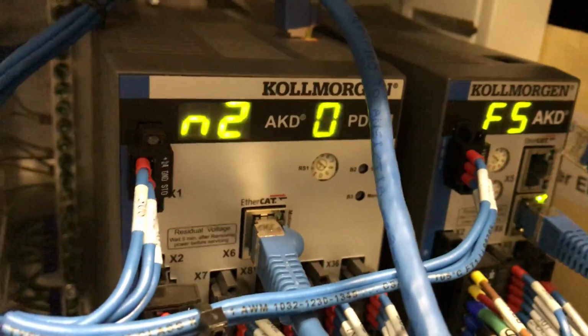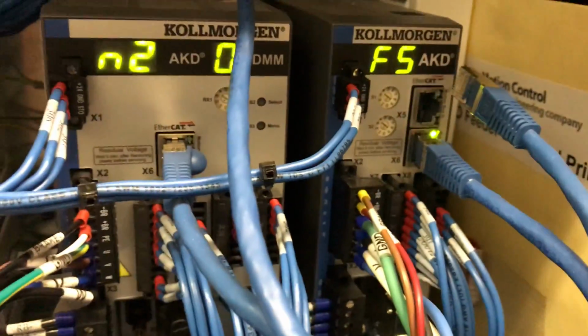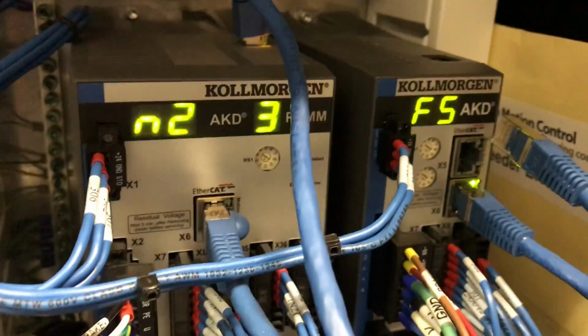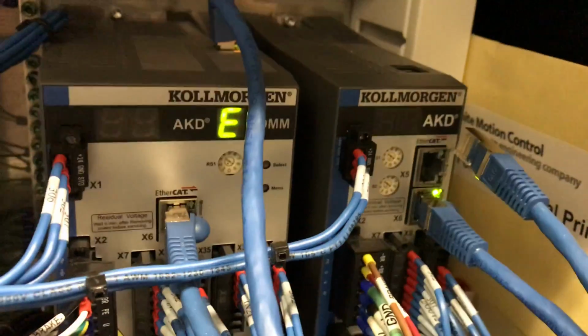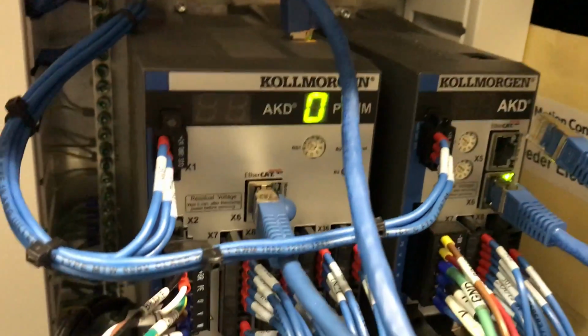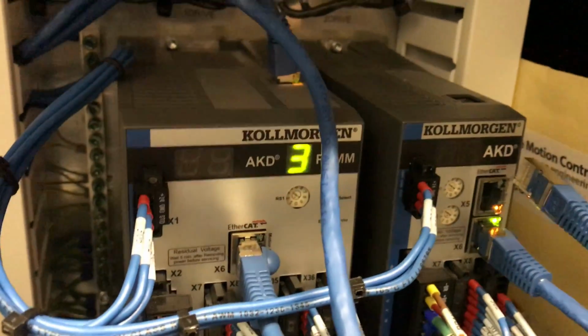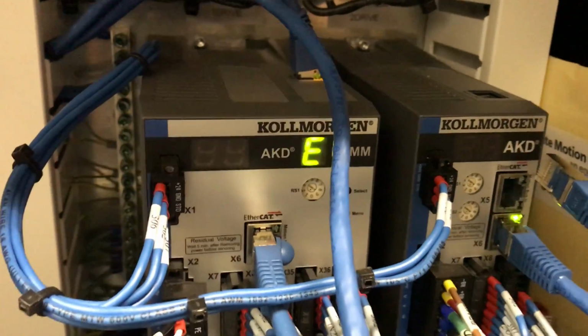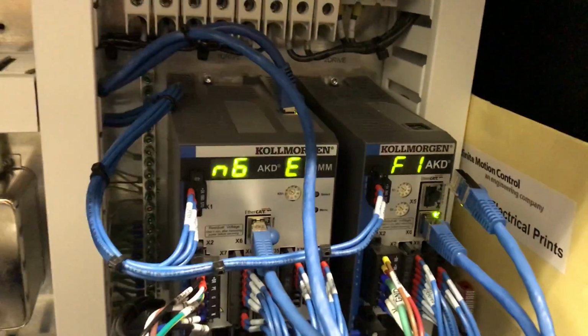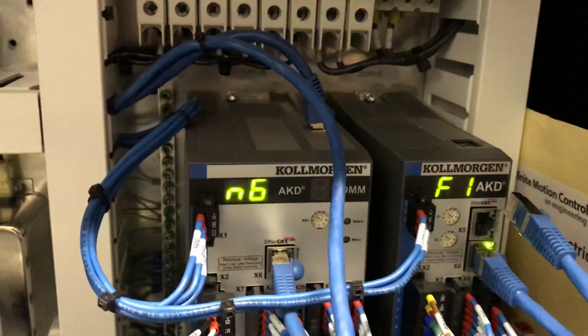It could be that the EtherCAT communication has failed, which it has in this case because I unplugged it, or it could mean that one of these devices has failed. There are other codes as well. Another one that's common is E33. That means that the configuration isn't what is expected, so it could mean that perhaps the remote I/O isn't in the communications link. Other things can happen. So these are the codes. These are where you can find them.